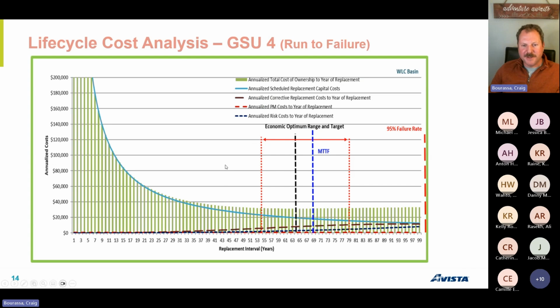We put all this information together, condition assessment, the risk assessment, and this is our life cycle curve. Nowhere near as pretty as the last one, right? There's no economic point that it's economically viable to replace this transformer between 52 years and 80. So why don't you replace it at 80? It's basically run to failure is what we see when we look at this graph, we run them to failure. So that's what we need to drive our maintenance to.